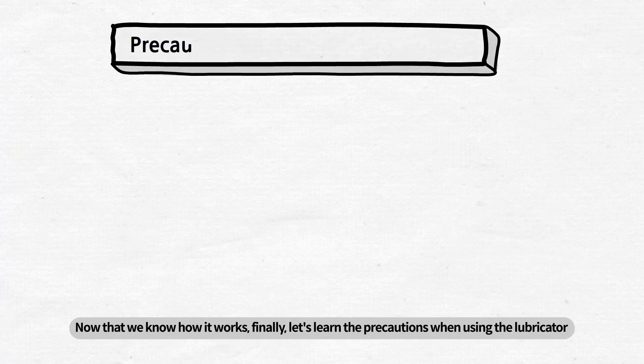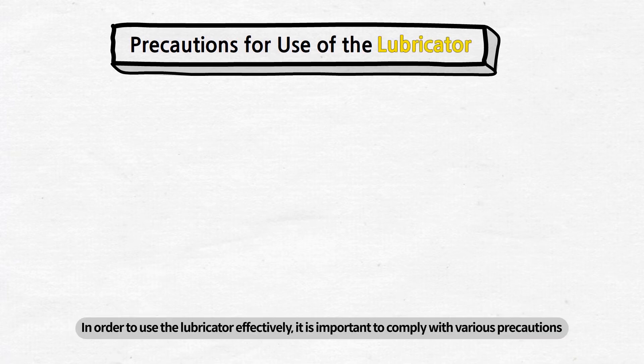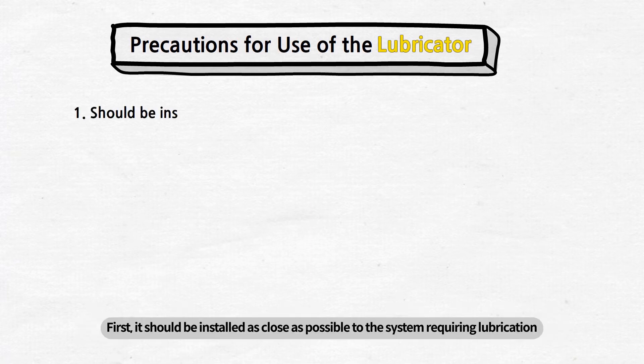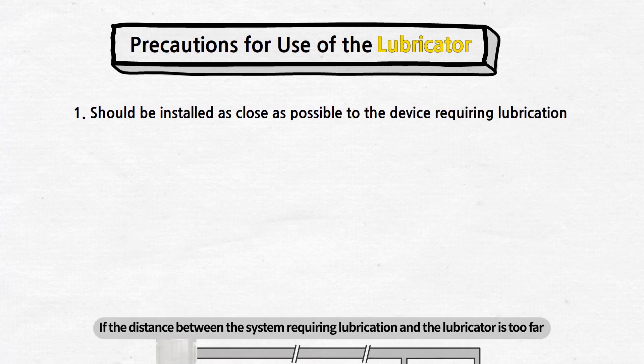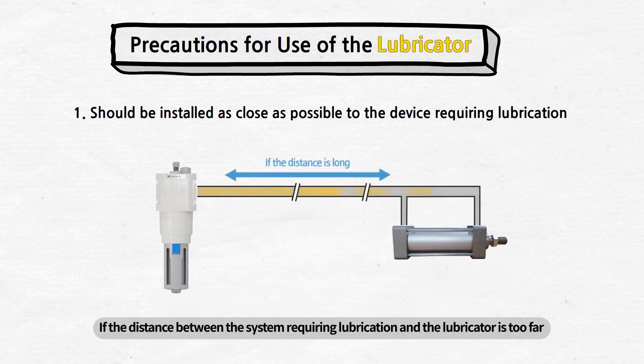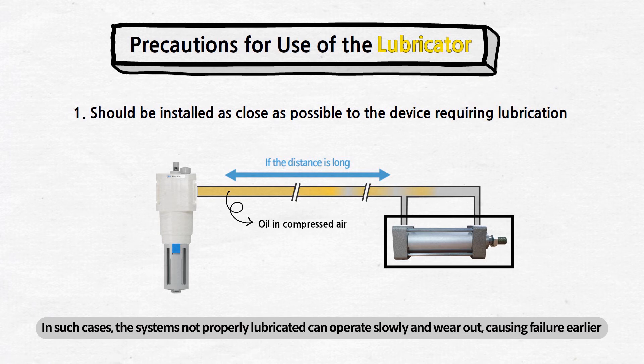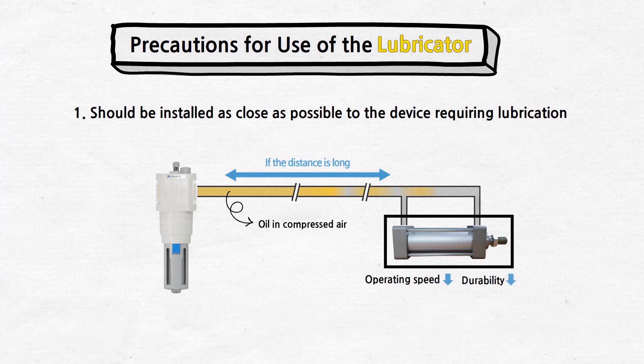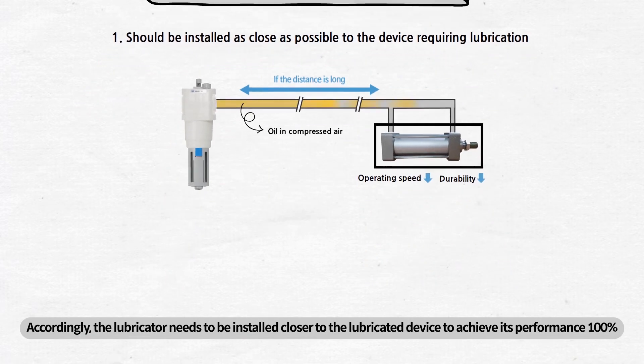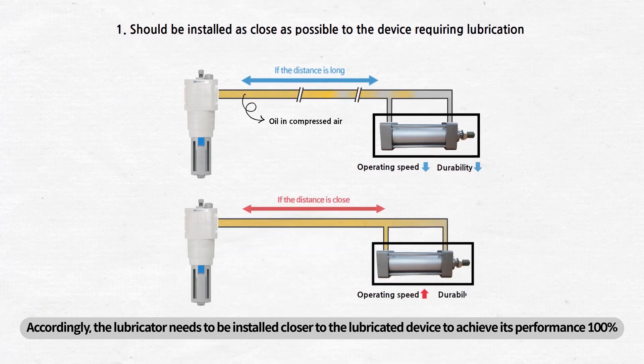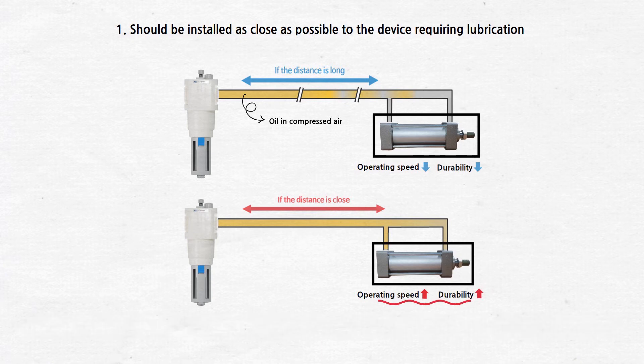Now that we know how it works, let's learn the precautions when using the lubricator. In order to use the lubricator effectively, it is important to comply with various precautions. First, it should be installed as close as possible to the system requiring lubrication. If the distance between the system requiring lubrication and the lubricator is too far, the oil may not reach the system. In such cases, the systems not properly lubricated can operate slowly and wear out, causing failure earlier. Accordingly, the lubricator needs to be installed closer to the lubricated device to achieve its performance 100%.